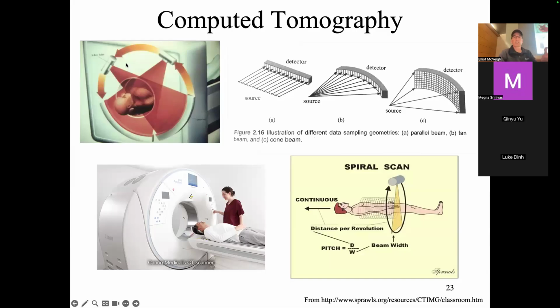The geometry of a CT scanner is I have a source of X-rays, I have a detector over here, and it's on a gantry that can spin. And so my source and detector remain fixed with respect to each other. However, they rotate with respect to the patient. So they get different angle views through the patient.